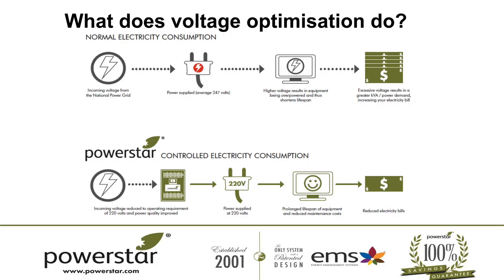What we tend to do is give you the correct voltage supply to your site. We don't want to go under or over supply with voltage. With over voltage supply, electric motors will run hotter with no additional performance — that excess energy is used as heat and the life cycle of that equipment will fatigue and run shorter. You'll be up for capital replacement, R&M will go up, your maximum demand will go up, and your total power bill goes up. So your total energy cost, facility maintenance, running costs, capital costs, and depreciation all increase — a bundled situation from being overpowered.